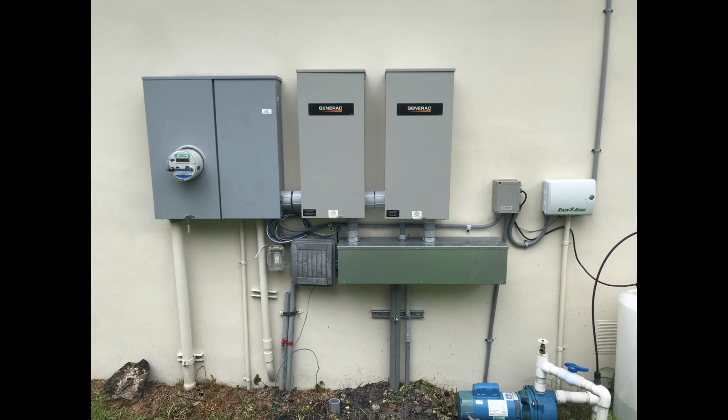And what they do is when the generator gets a message that for 10 seconds that you're out of power, it says, okay, I'm going to start up and I'm going to get myself up to my proper operating RPM, and moreover, my correct power and hertz cycles, 60 cycles, and it will then switch the connection inside each of these two switches from the dead, in essence, utility connection down to the generator connection.